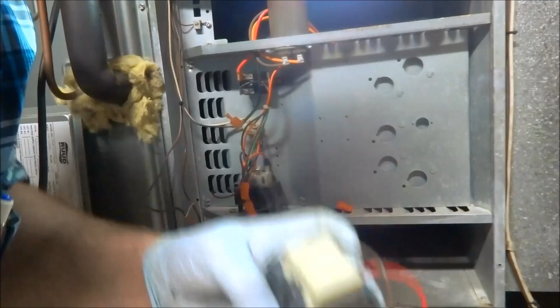Take that other screw out of there, I think. What burnt the transformer out was the bad contactor, which in turn shorted out the transformer. I was getting no power to it. You could smell it's burnt. You could sniff it. I don't know if you guys can smell, but you can smell if it's burnt. Okay, and then I got my 24 volts here. We'll see which one is higher, and that's the one I'll use for the red.